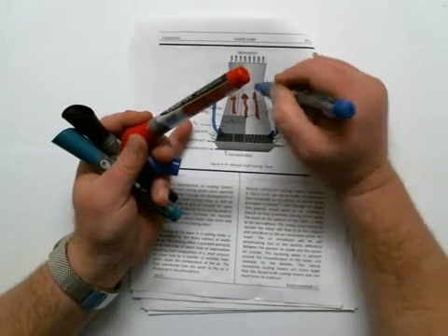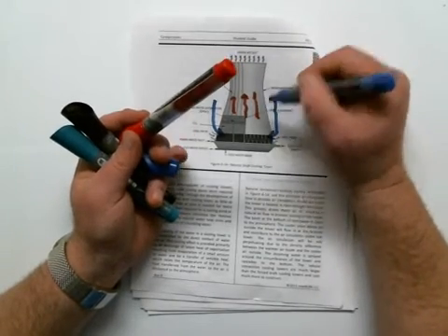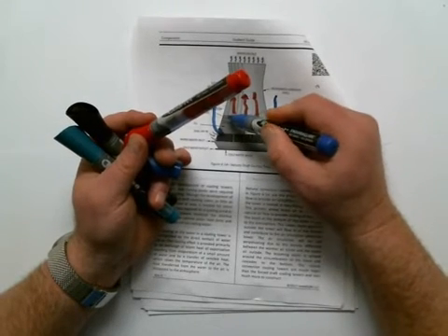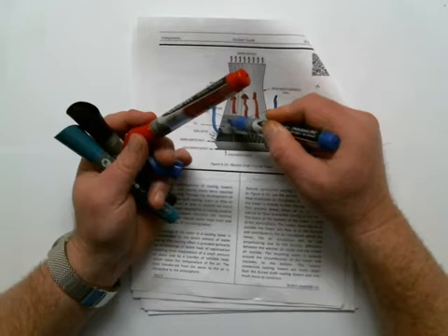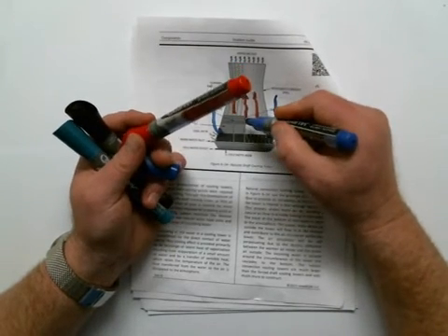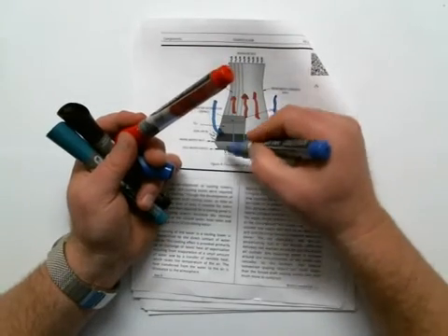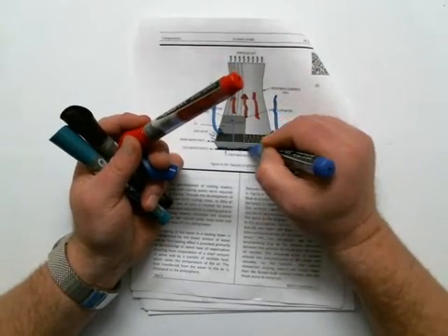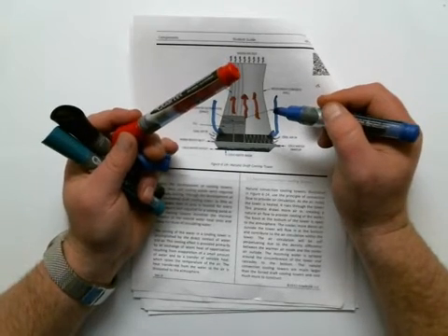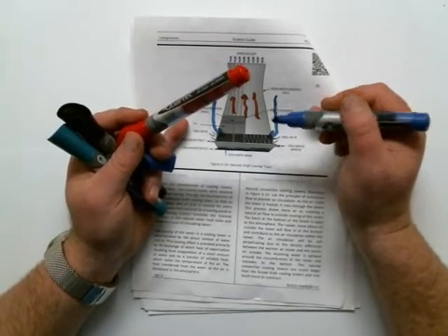Very, very expensive, these cooling towers. No moving components or anything. The warm water distribution up here, they increase the surface area using a fill material, which is generally some sort of plastic. And you can see the flow path here, and then you saw the outlet, the cool water ends up being the suction source for circ water intake pumps. So they're pretty cool, very expensive.